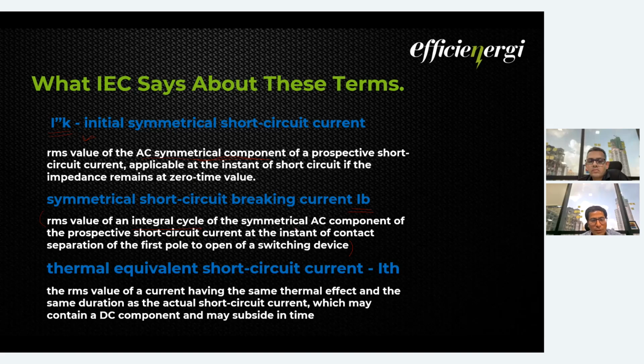Then the thermal equivalent short circuit current is there, ITH. If we are doing a lot of coordination and short circuit studies, many times this ITH current is not checked for the breakers, or for that matter the transformers or cables. We don't see much of this. We only check what my breaking capacity and my making capacity are. That much only we see, and the rest of the things we really don't check.